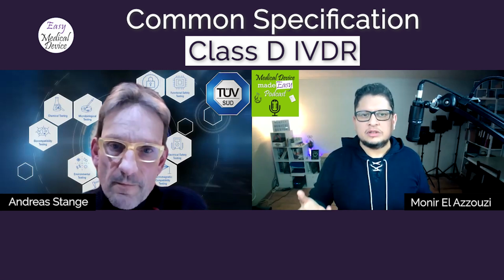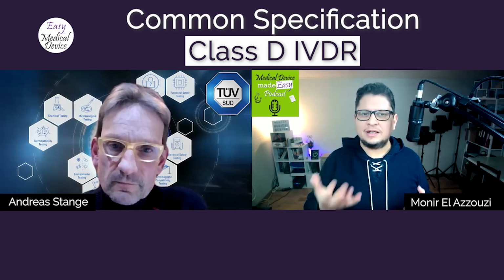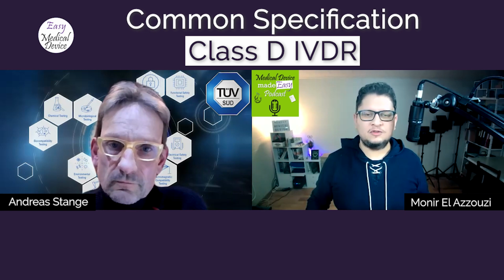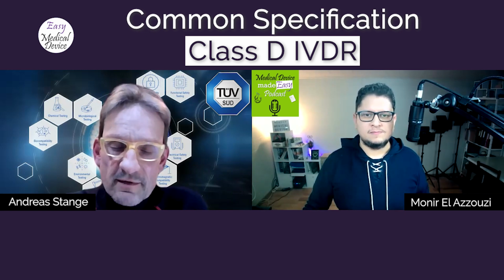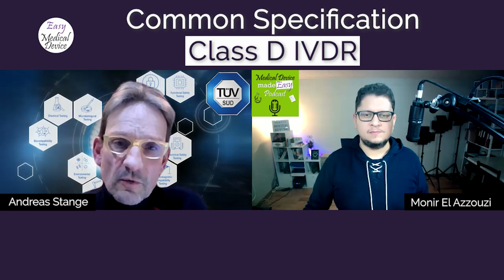In terms of common specification, we talk about that under IVDR. But was there also common specification under IVDD for some of those products? Yes, for the Annex 2 products, there were common technical specifications, which must be met by the manufacturer in order to get the certification of the device.